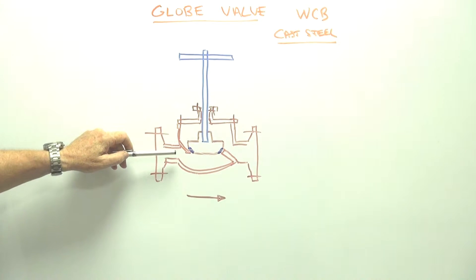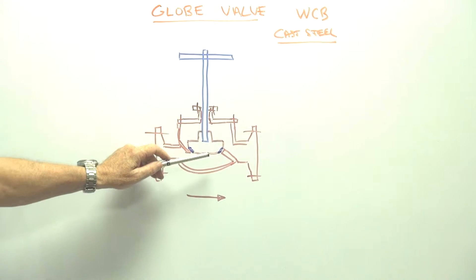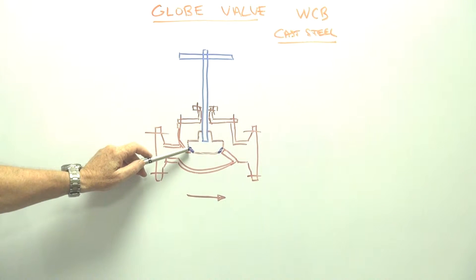ANSI is the ones that we normally stock. This face on here has a hardened stellite seat because the steam coming through is very abrasive. This is good for steam and other applications but usually it's used on steam at high temperature.